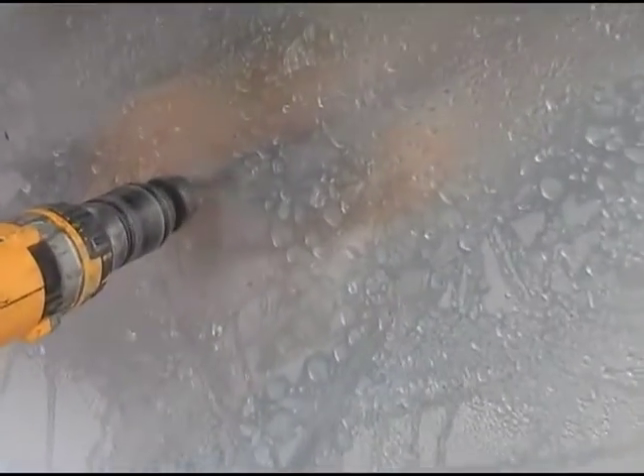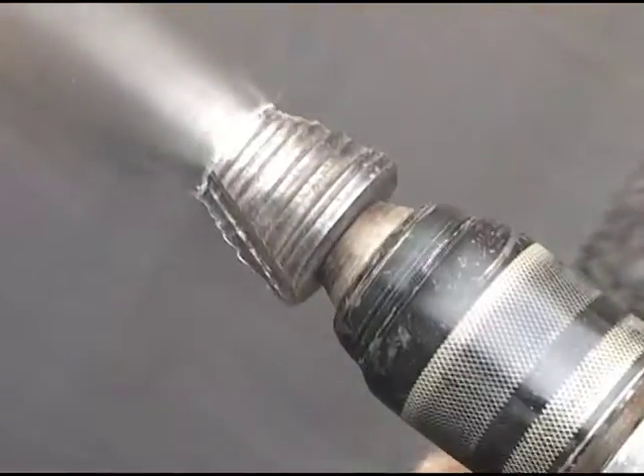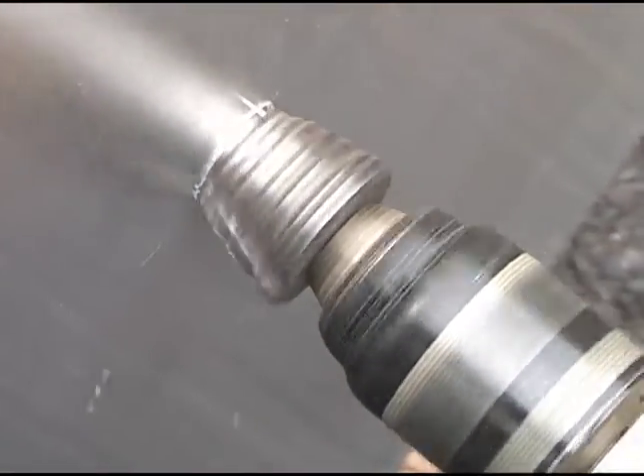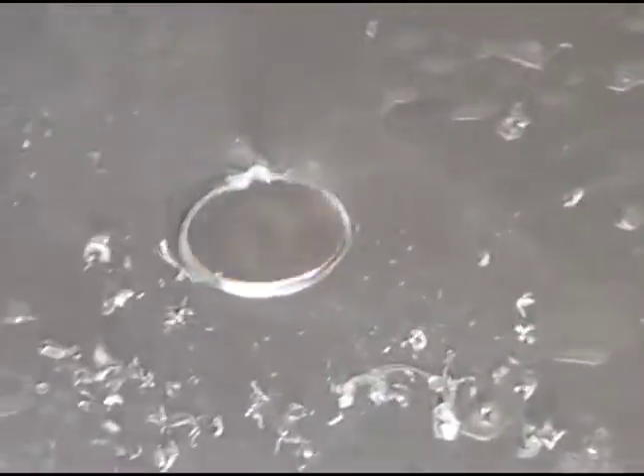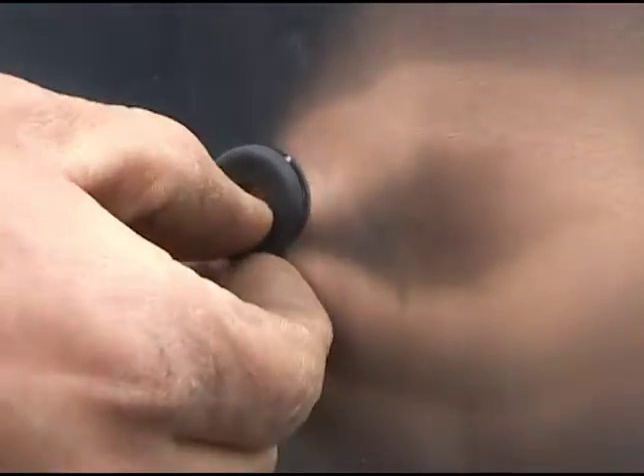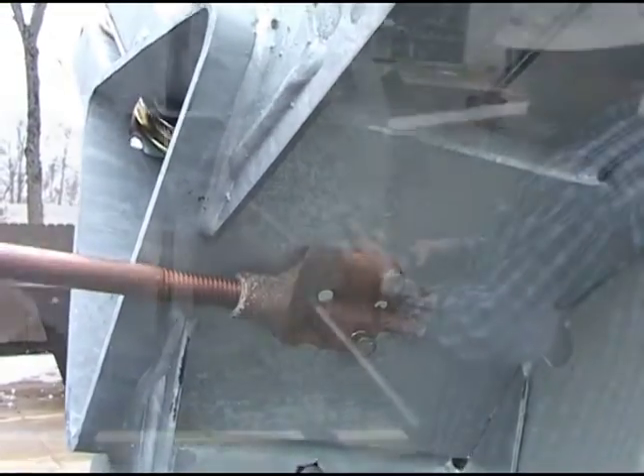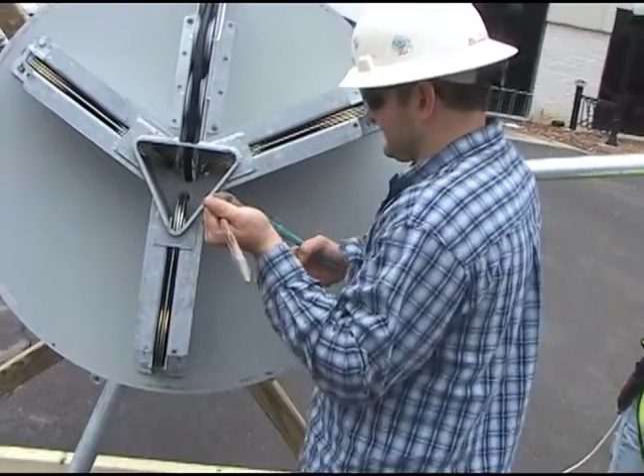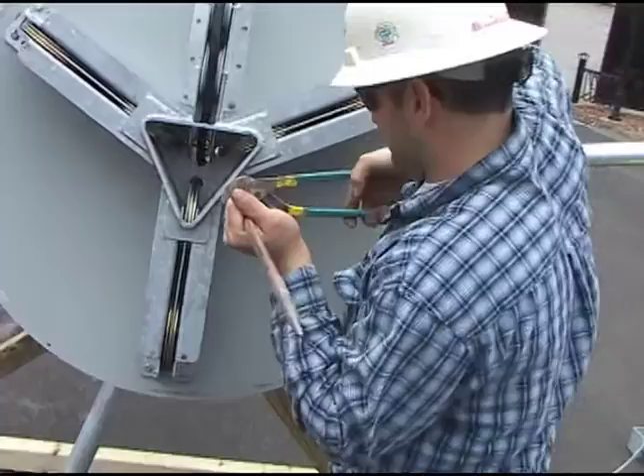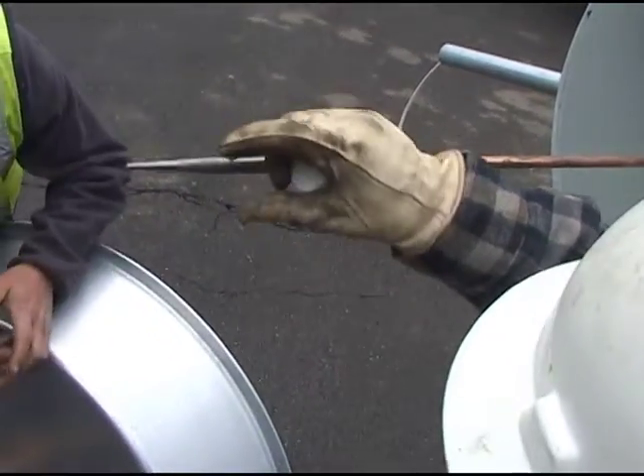If a lightning rod is used, the head frame cover has an indentation in it for the location where the rod goes through it. A 7/8 inch hole needs to be drilled and deburred at the position of this indentation. A rubber grommet is supplied to insert into the new opening. The rod is then screwed into its mounting bracket. Put some lubricant on the grommet and rod for a smooth installation.